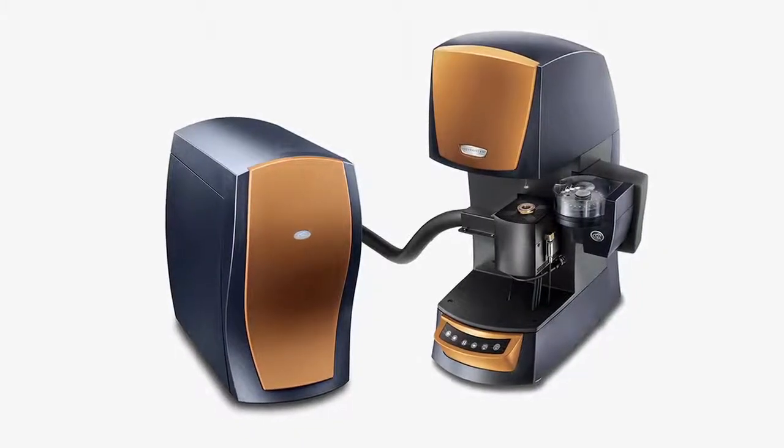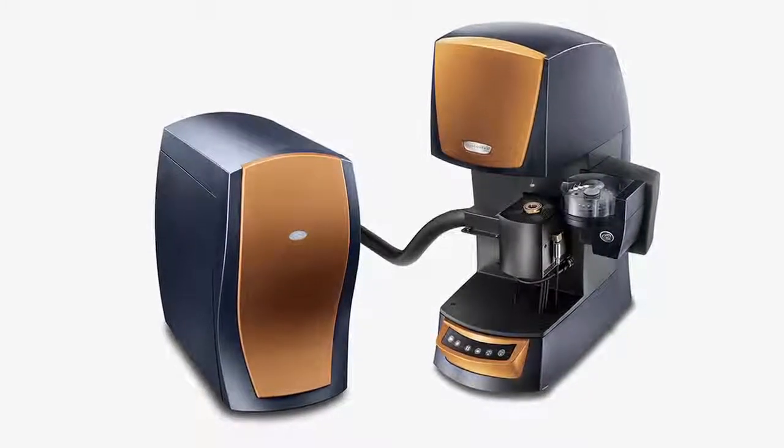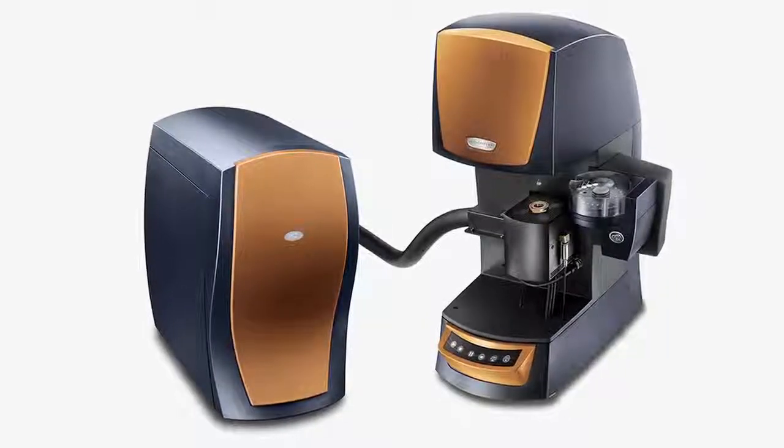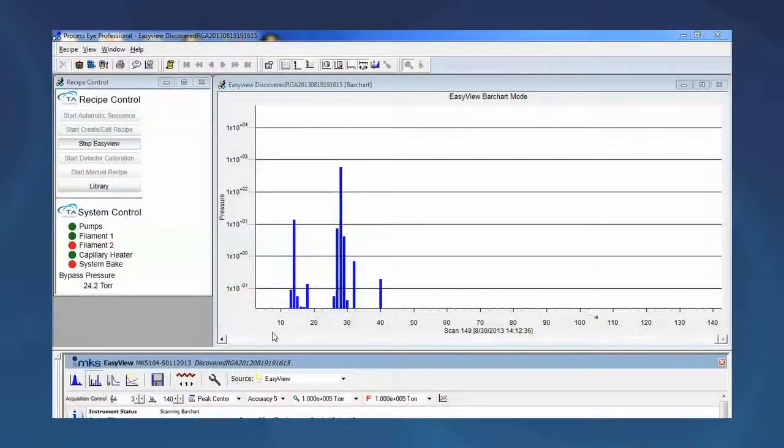This tech tip continues a series for the Discovery Mass Spectrometer. We will create a simple peak jump recipe for the analysis of water evolved from calcium oxalate monohydrate and use it as a measure of the performance of the detector. We could create a simple peak jump method for analyzing calcium oxalate. We will use this as a means of measuring the response of our detector.